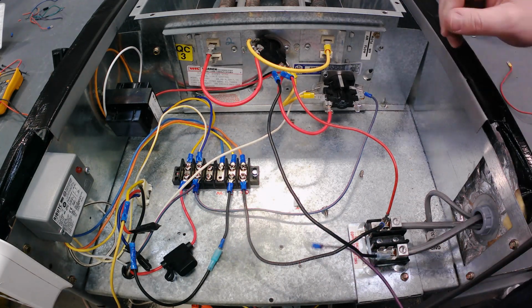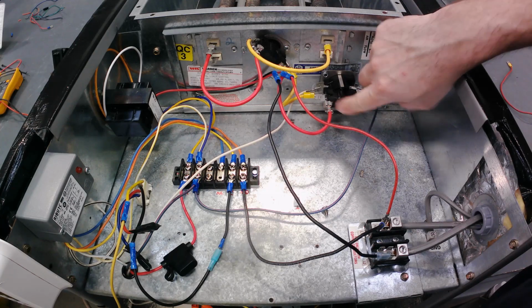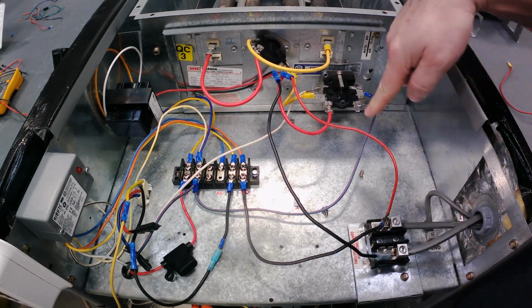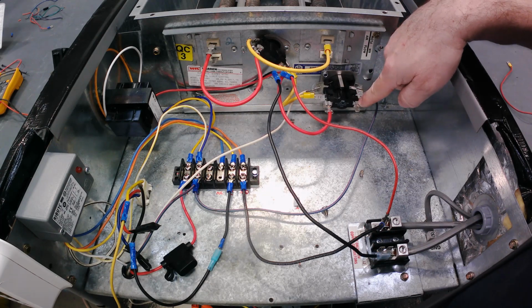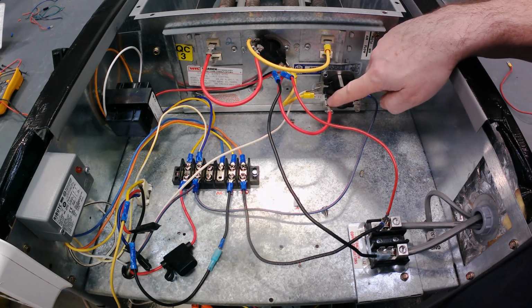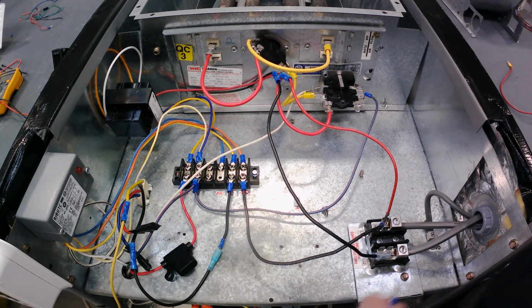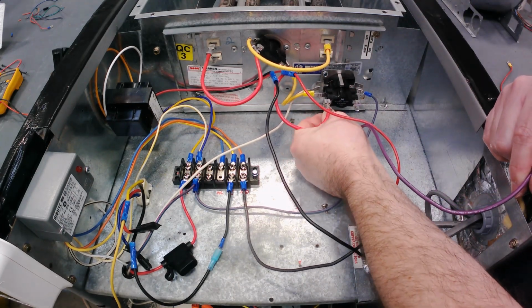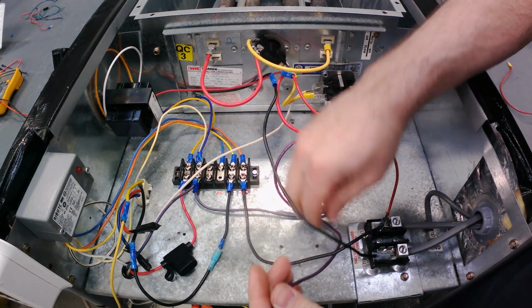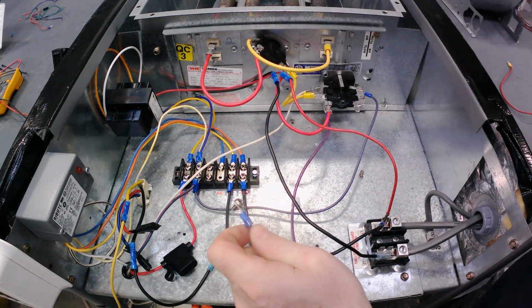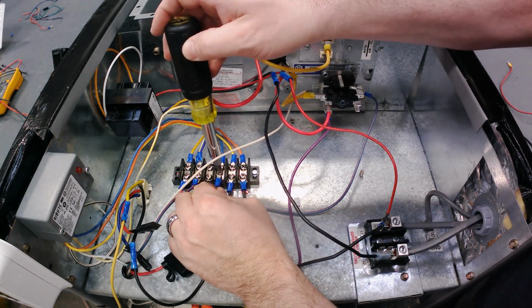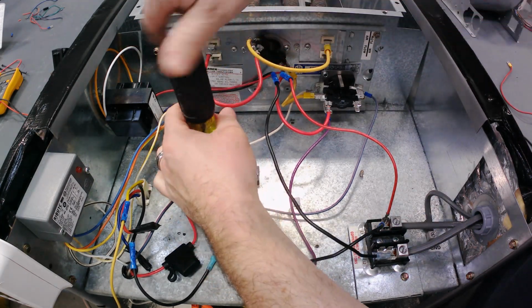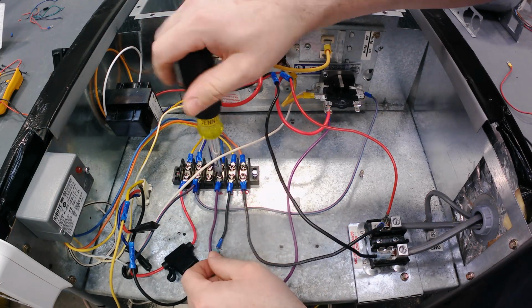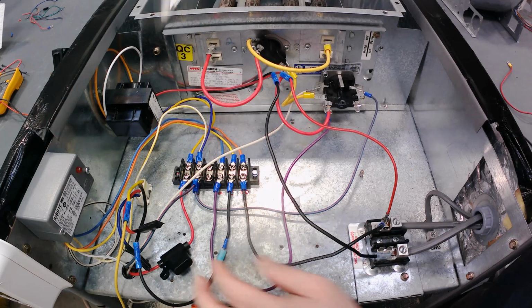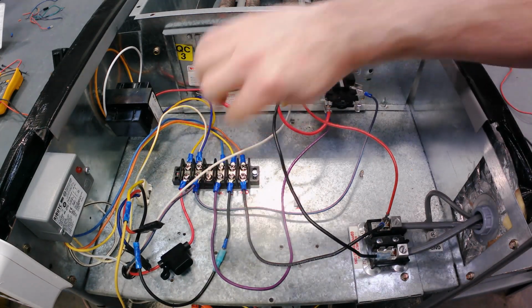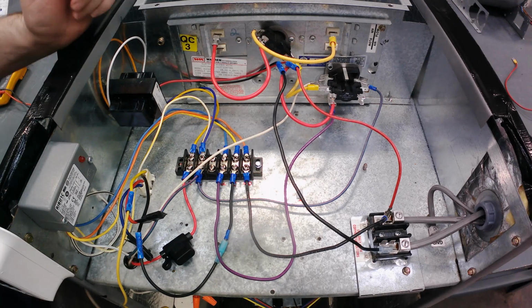And then on the outlet side of our switch, we're going to have L1 coming from this terminal block into the sequencer. When the switch closes on a call for heat, as power goes out to power the heat strip, power is also going to go out through the normally closed terminal into our RIB relay. So that's how that'll be wired up, and it'll make it real easy for us to do voltage checks here in a little bit. So basically the RIB relay is set up.